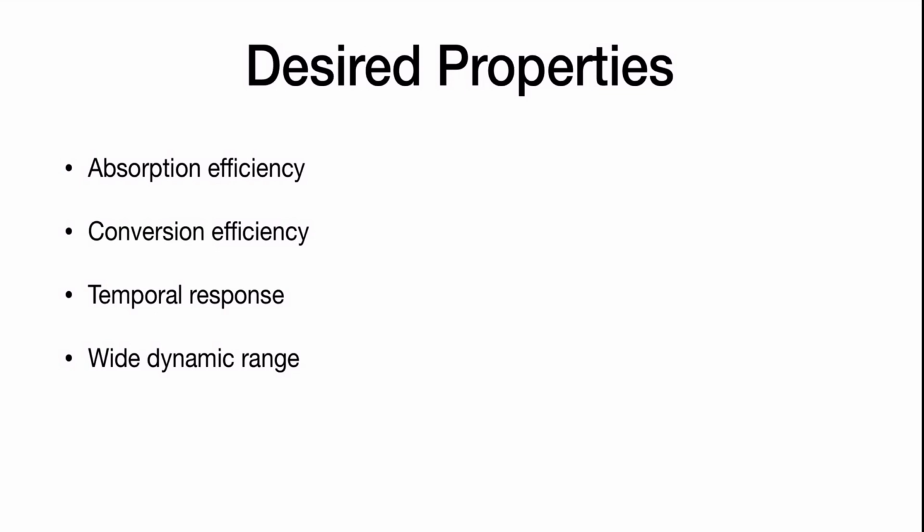In particular, when you're dealing with fluoroscopy, where you want to take a series of frames, you want your detector to be ready for the next frame. Okay, and obviously one other desired property is to have a detector that is able to catch a wide range of radiation. Of course, when you're dealing with a particular anatomy, you know what kind of output radiation to expect, but the wider the range, the better. And a wider dynamic range means the contrasts between the different types of radiation are going to be much more defined, which means our pictures are going to be much clearer. Okay, so these are the few desired properties of a detector that I thought might strike a chord with us.